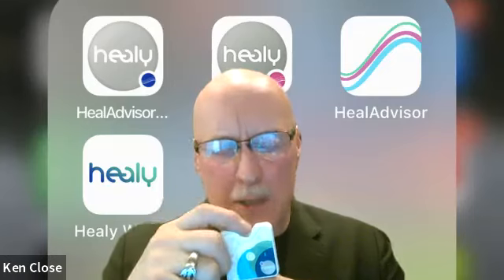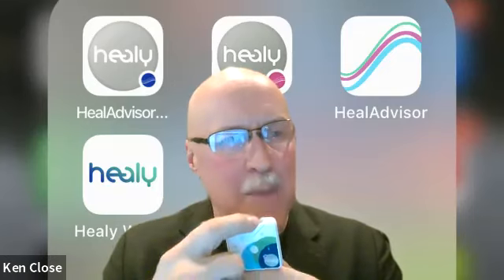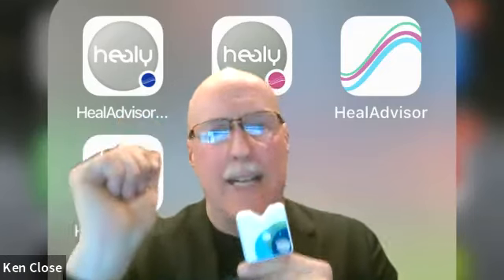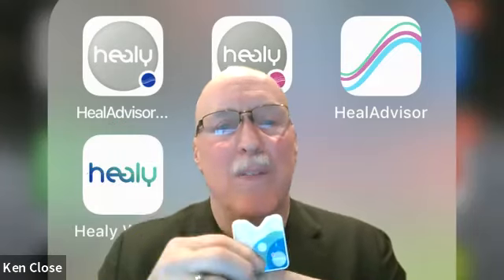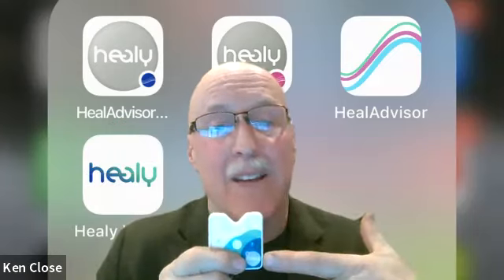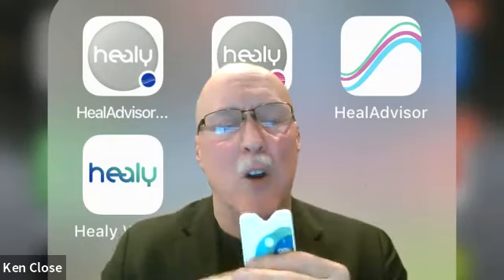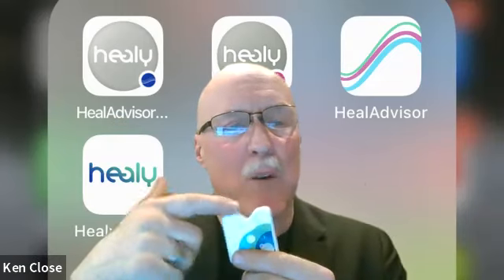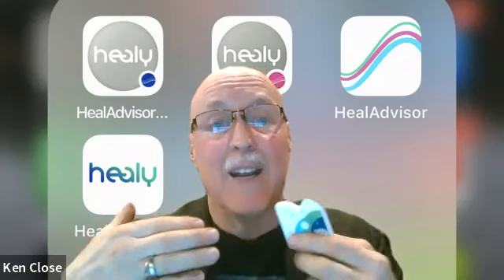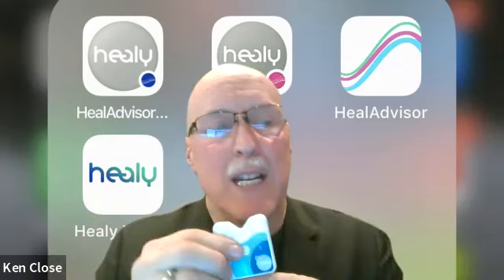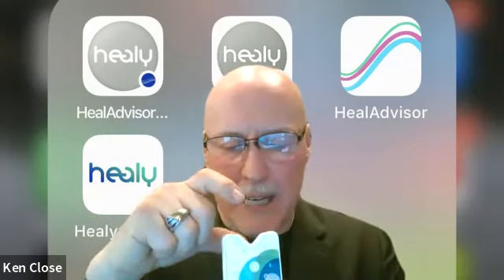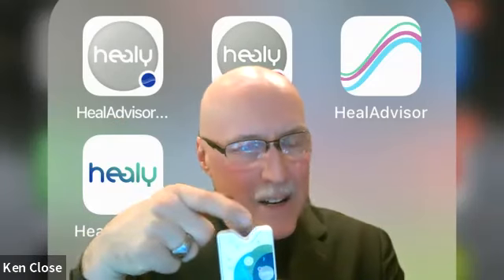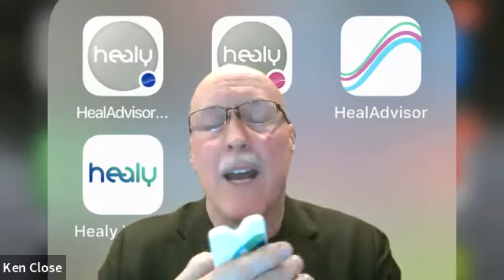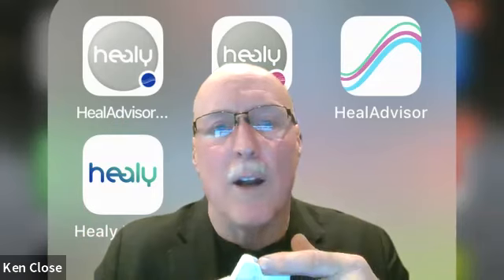You're not supposed to have it plugged into the wall outlet at the same time you have wire electrodes connected to your body. So there is a potential path, very, very rare, of current flow from a wall outlet into the body when you have wires connected in that proximity. So it's designed so that you cannot plug in the wires and the charging cord at the same time. That's why it's designed in that way. So you can't run the pink dot while it's plugged in. It won't work.